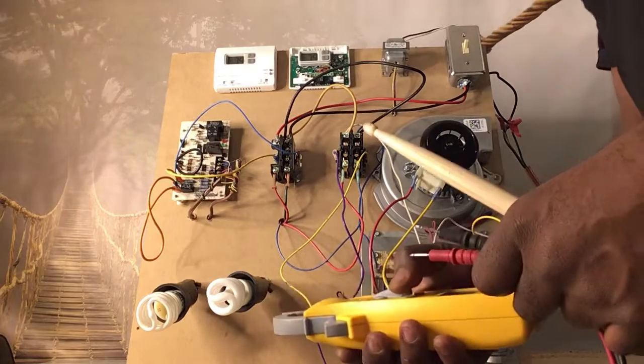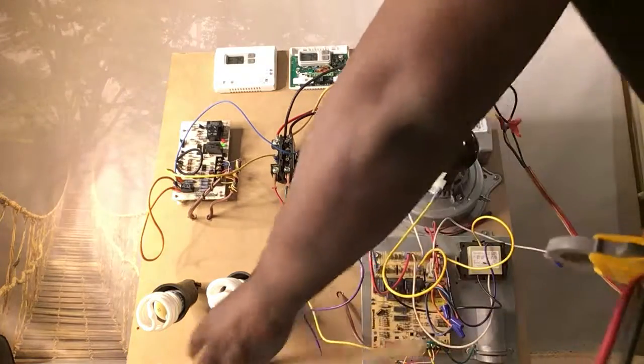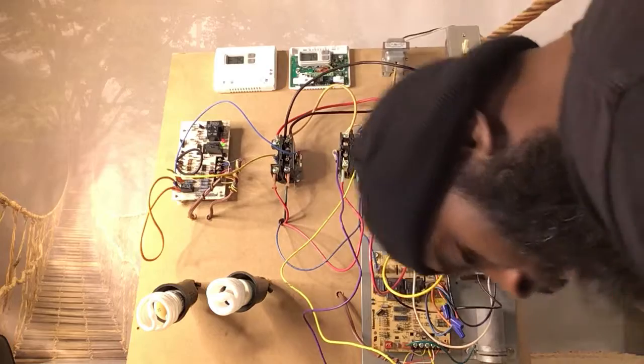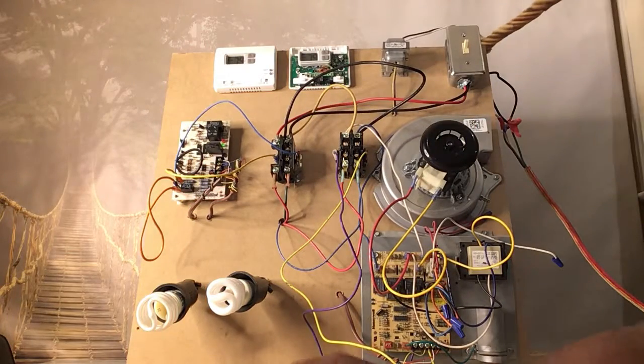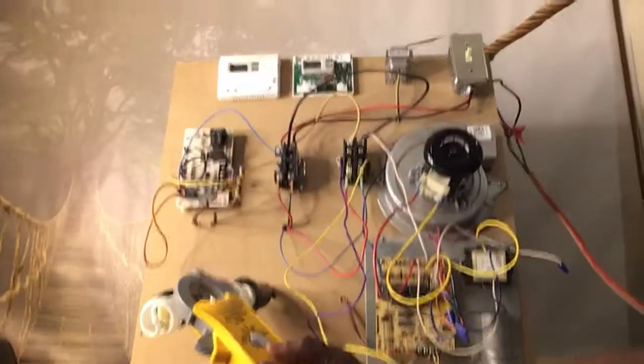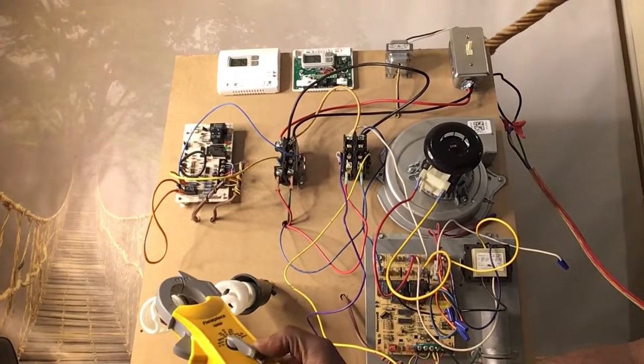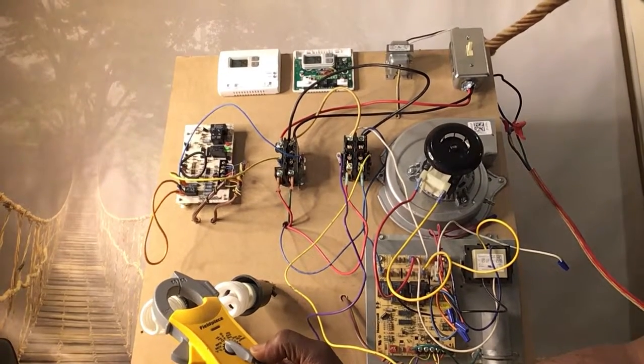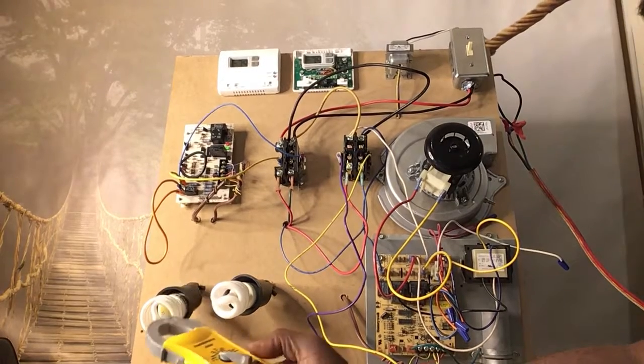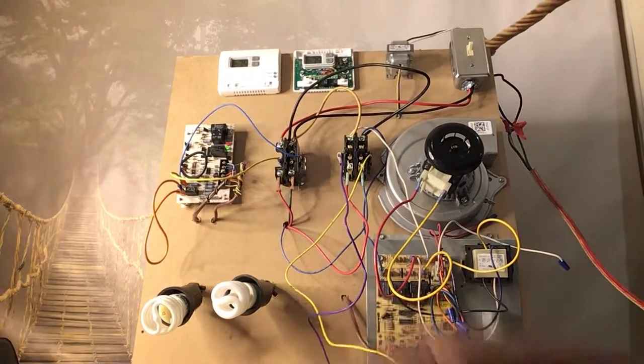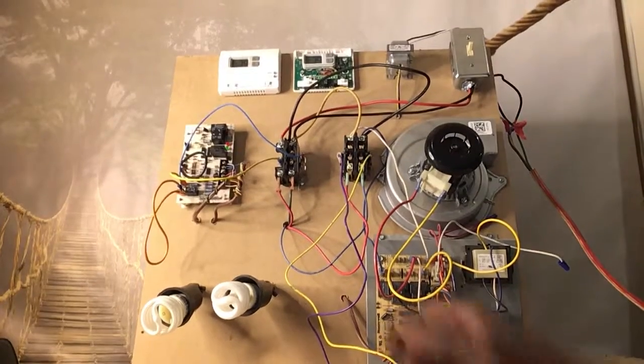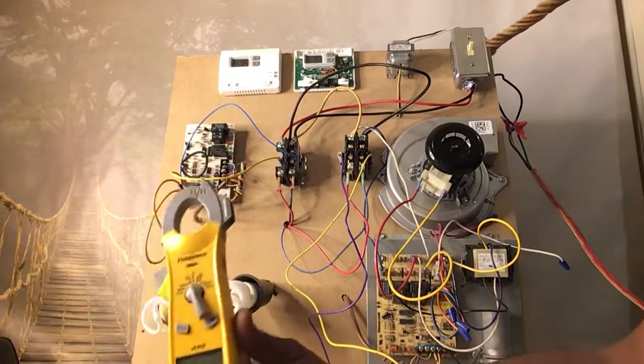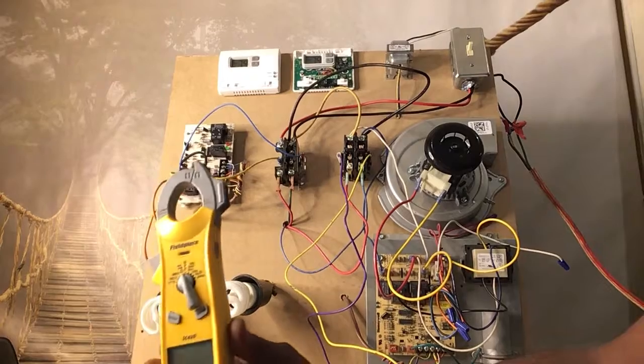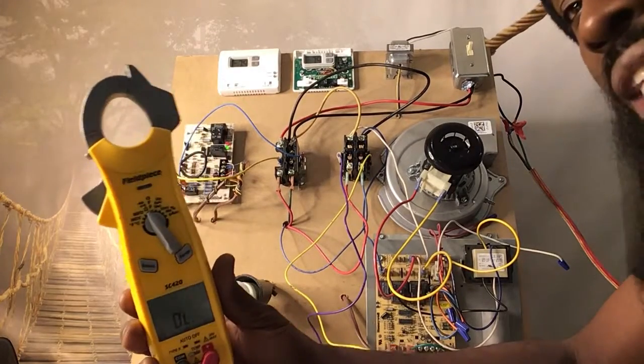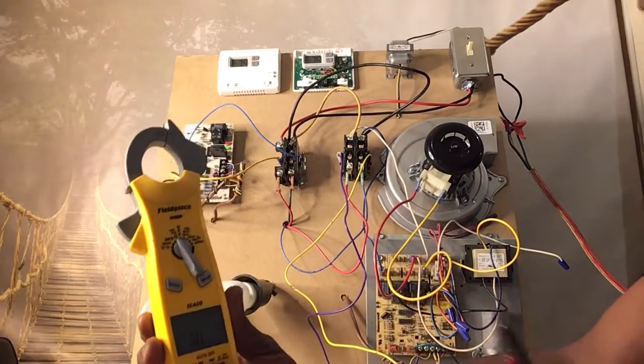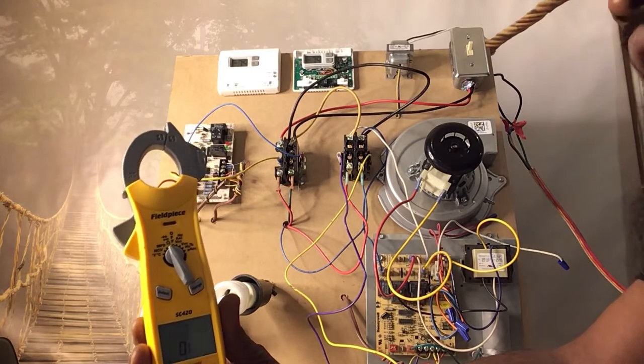Also want to go over some simple stuff with the meter, because the meter is super important. What you can also do, which is imperative on the troubleshooting side, is continuity checks. Continuity checks are super important, and what a continuity check does is it allows you to verify whether or not your wire has any break in it.